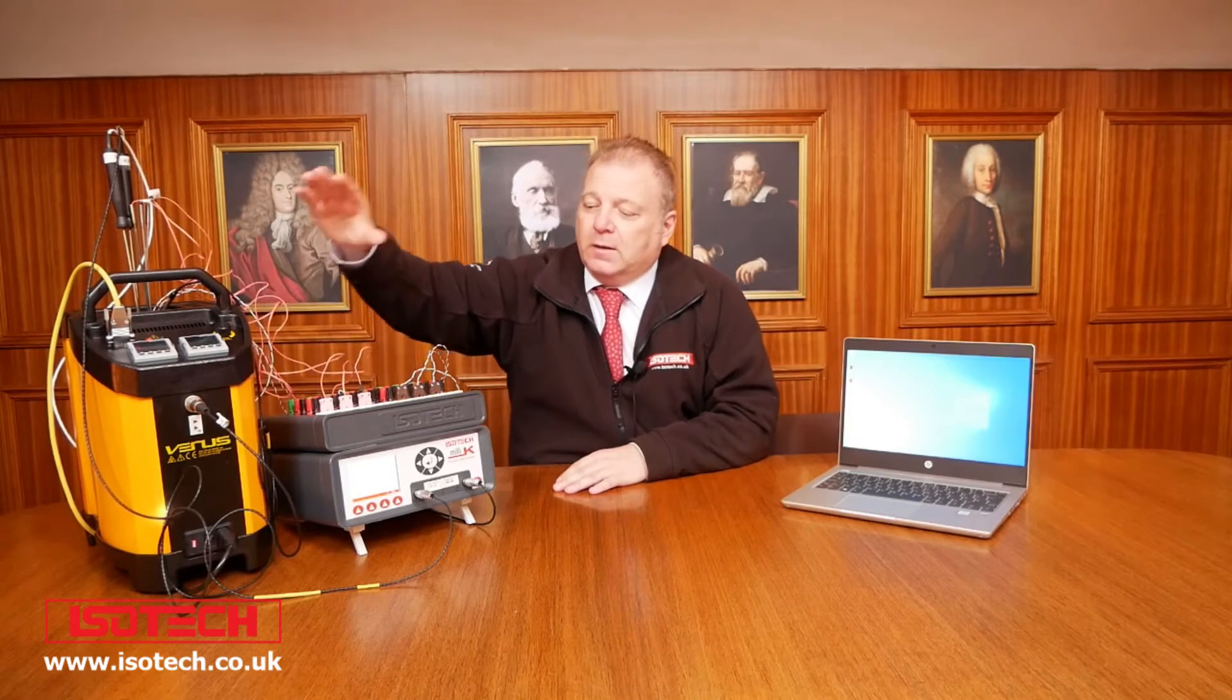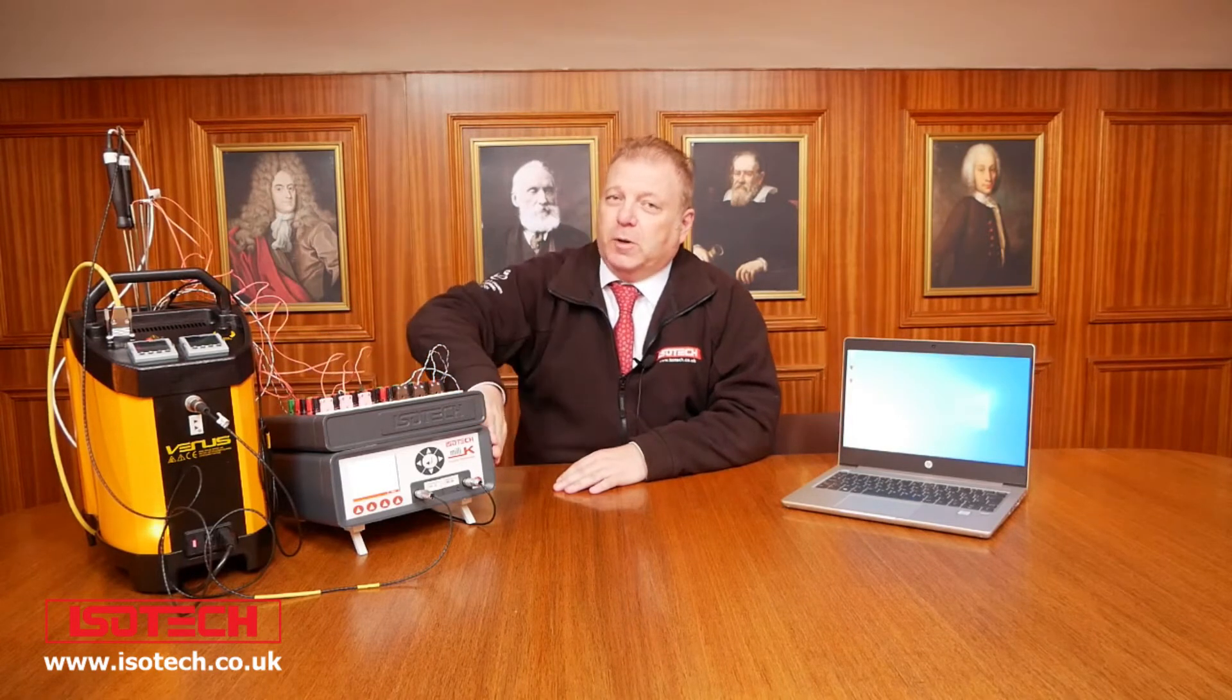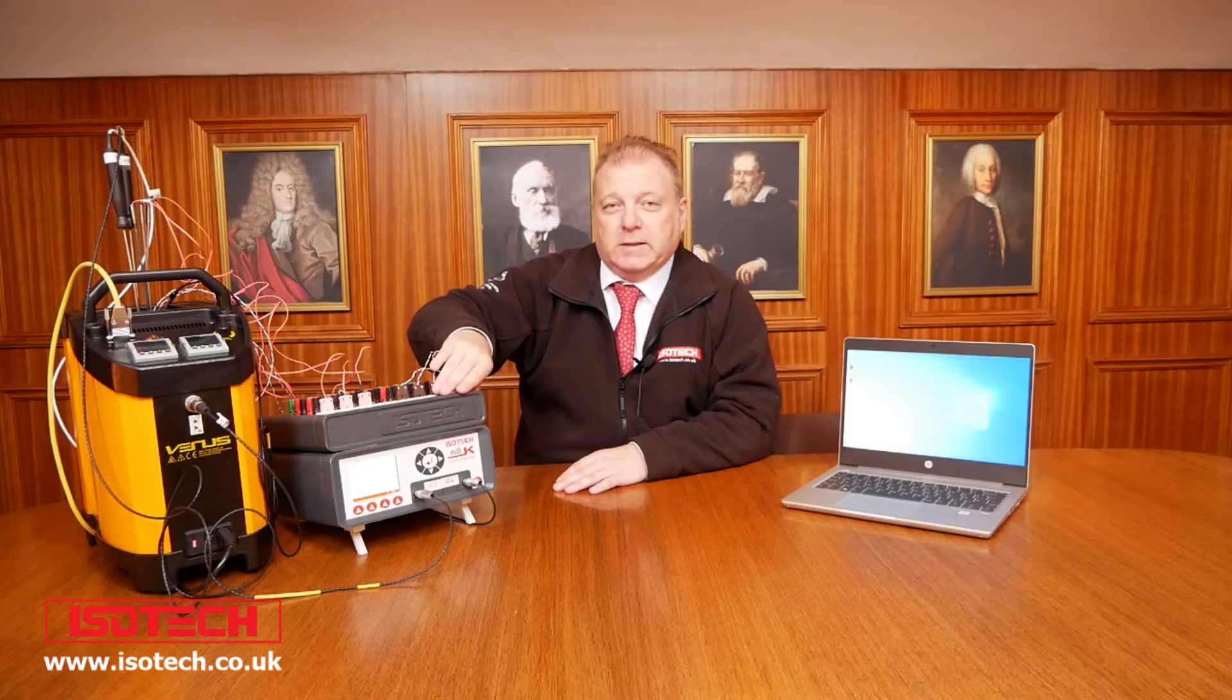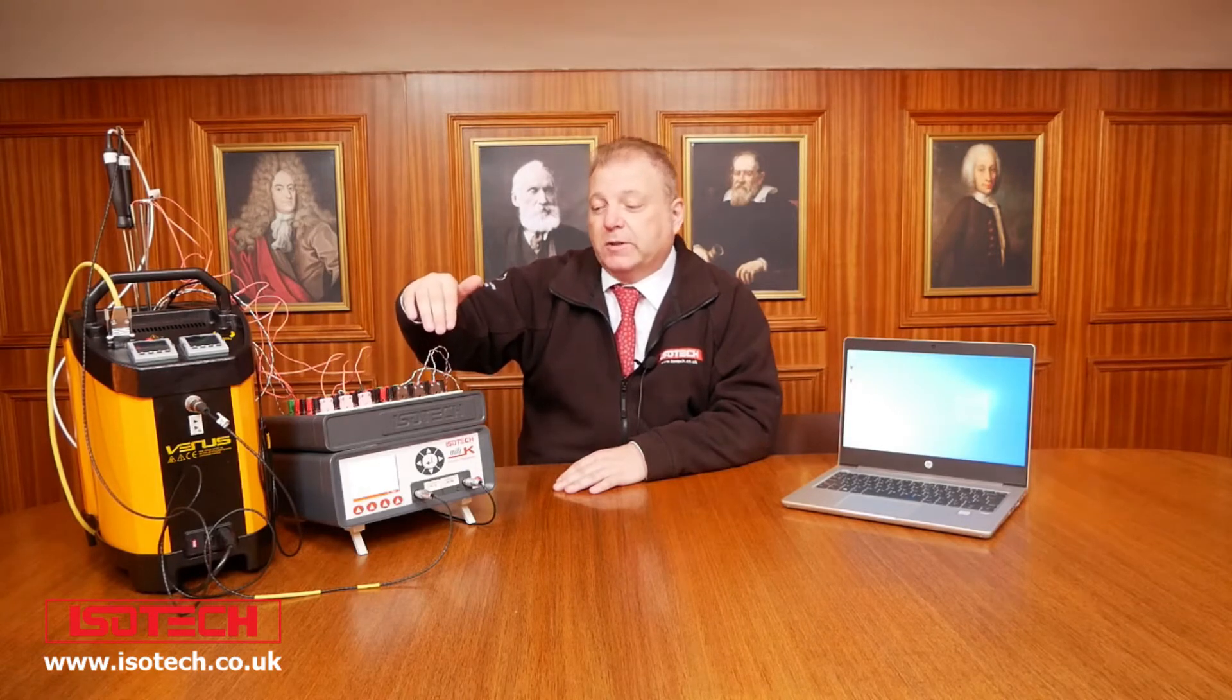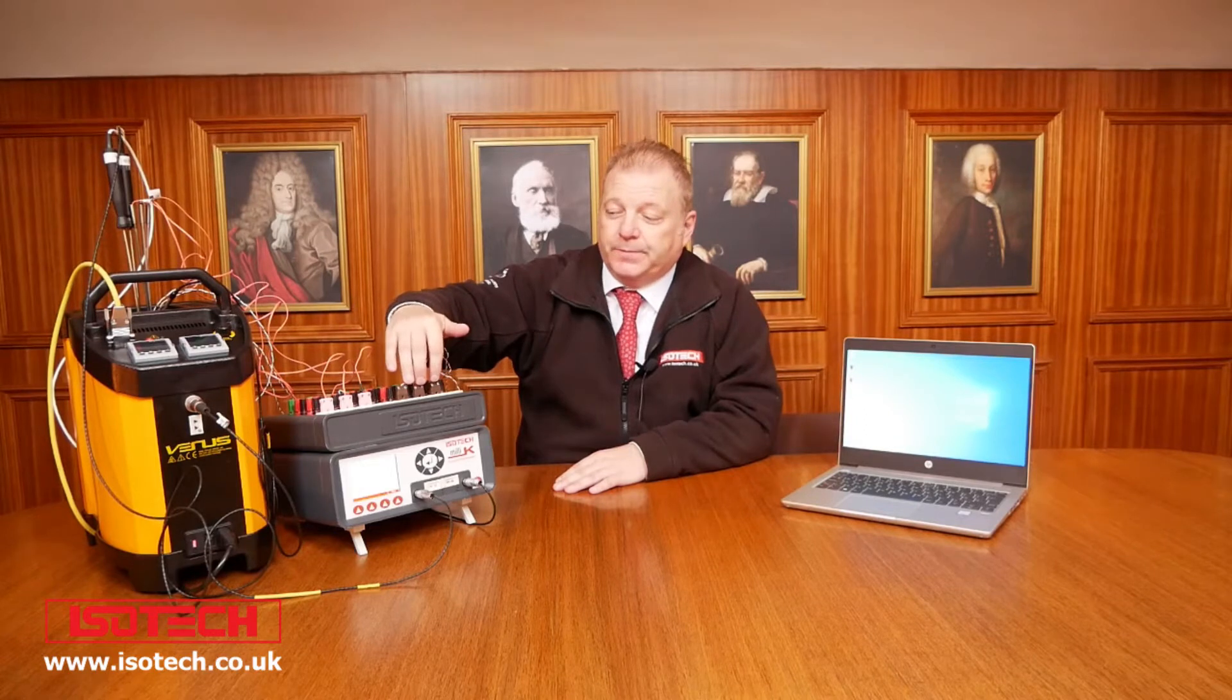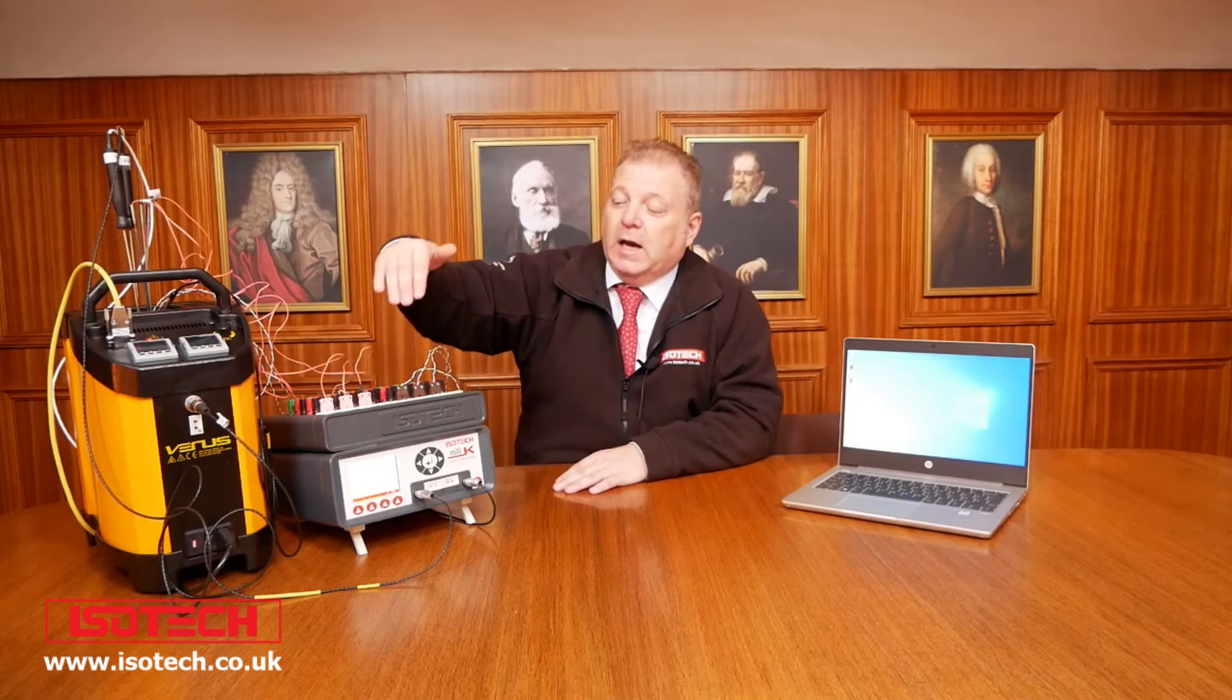So here we have a dry block calibrator, a precision thermometer and a milliscanner that can accommodate up to eight inputs. For the inputs today, we are going to calibrate three type T thermocouples, three type N thermocouples and a PT100.